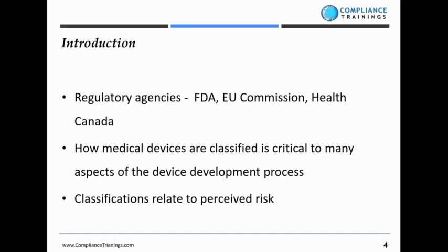Basically, every medical device is regulated in some way by the various regulatory agencies that govern them throughout the world, such as the FDA, the EU, and Health Canada. These regulatory agencies among themselves have defined sets of rules and regulations regarding medical devices to include how they are classified. The rules and regulations that might apply to your particular medical device really depend upon how your product is classified by each agency within the countries where you'll be marketing your product.